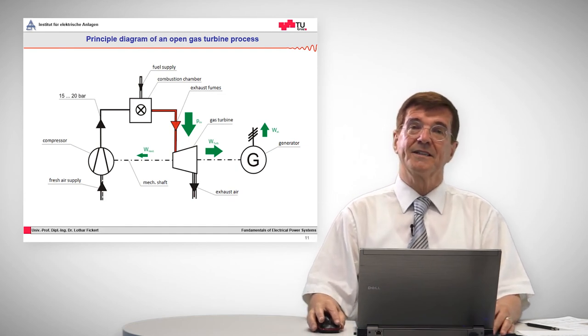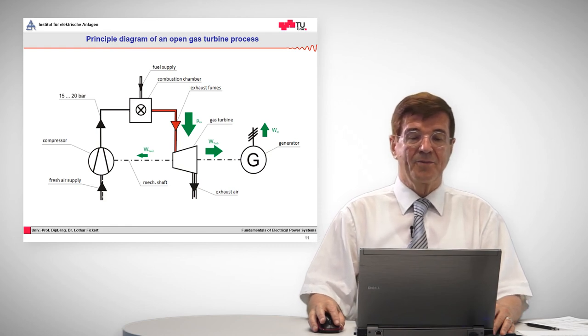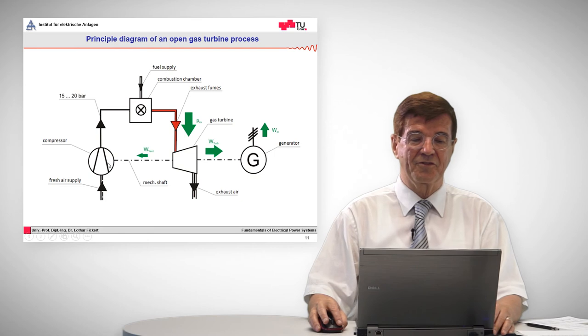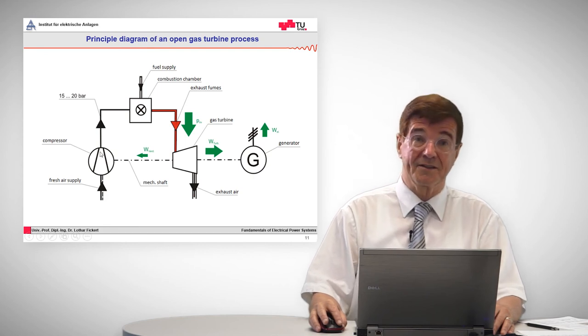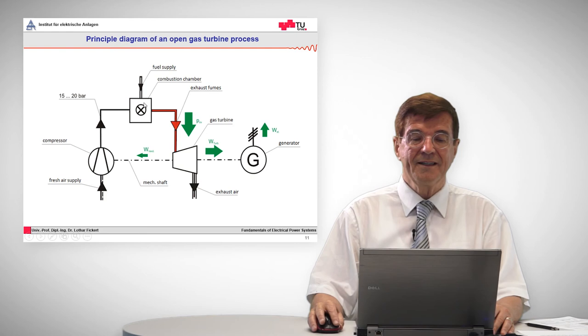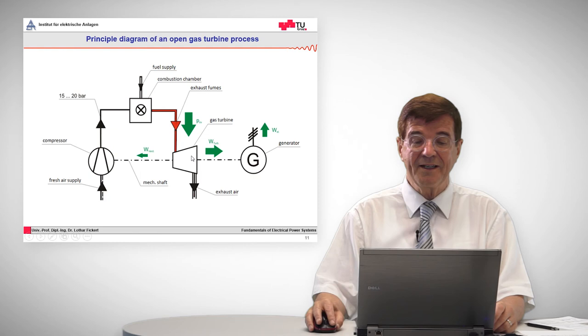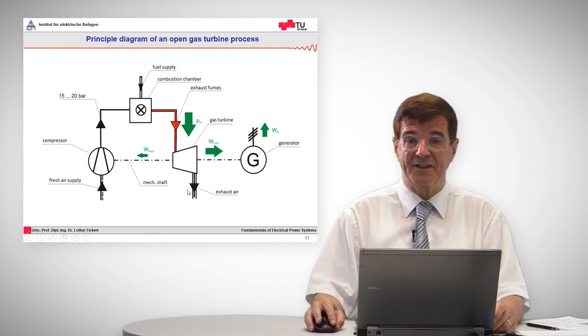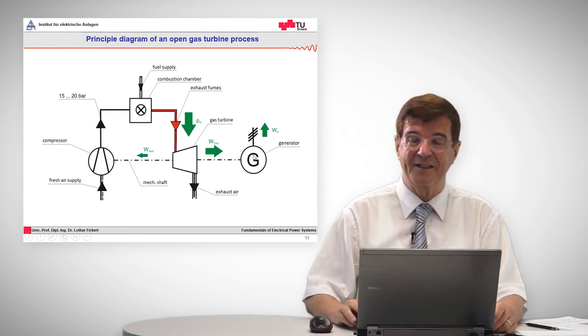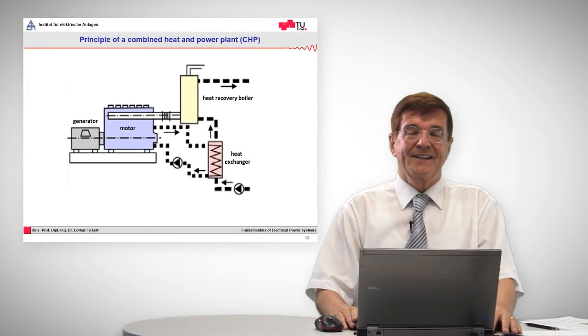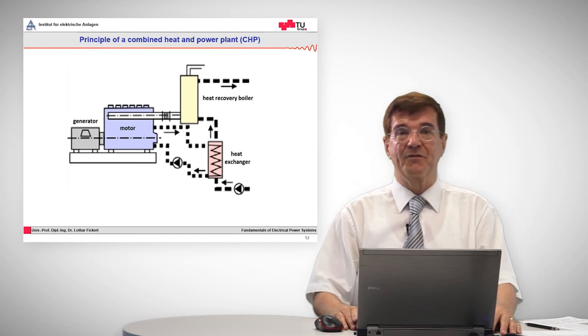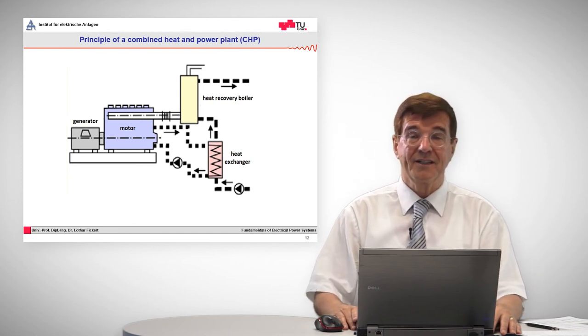Sometimes a thermal process can be realized in such a way that we have a gas turbine. The gas turbine is working in a similar way. First, we have a compression of the fresh air supply, which is something like the feed water pump in the steam circle. So we have compressed air, then some fuel is added and ignited, and it blows out to the right side of this combustion chamber into the gas turbine, and there the exhaust air with the exhaust fumes goes into the open air. And while the hot gas is expanding, it turns the generator, which in turn produces electrical energy.